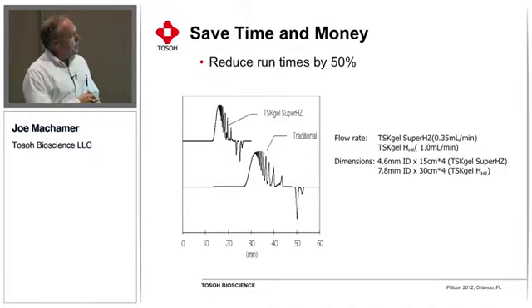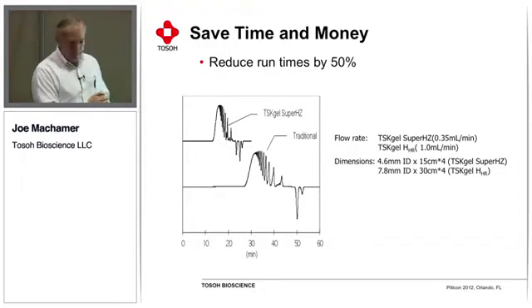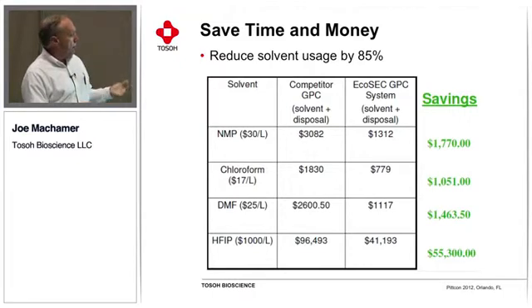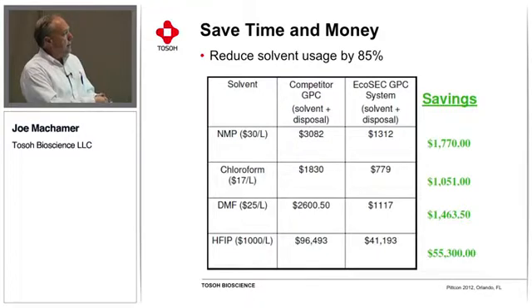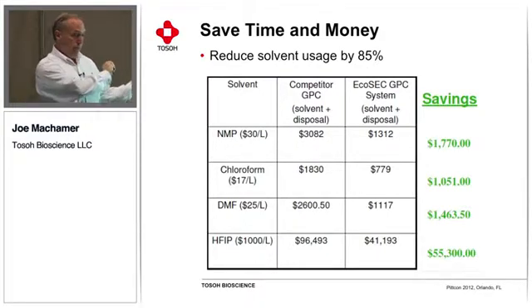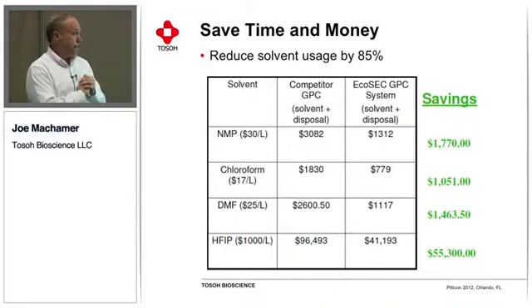And here's some chromatography simply showing a chromatogram with a conventional column versus the Super Multipore, or sorry, the Super HZ column. When run on the EcoSEC, we're able to maintain excellent resolution, but once again, this is on a smaller column, so very fast run times. And if you're using expensive solvents, something like HFIP, the ability to run at 1/3 of the flow rate and still have really good resolution can be a significant cost savings. So we have a customer for whom that was the main attraction to the instrument. He was using HFIP, which of course is very expensive, and the fact that he could reduce his solvent usage by 85% by simply choosing an EcoSEC GPC system made all the difference to him.